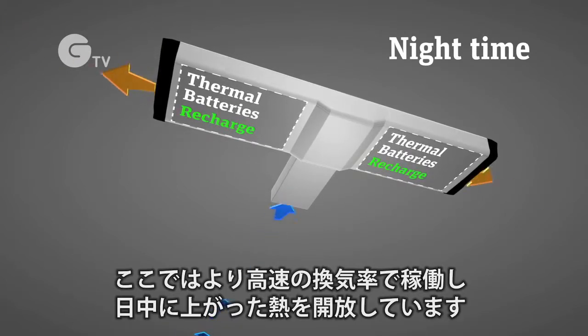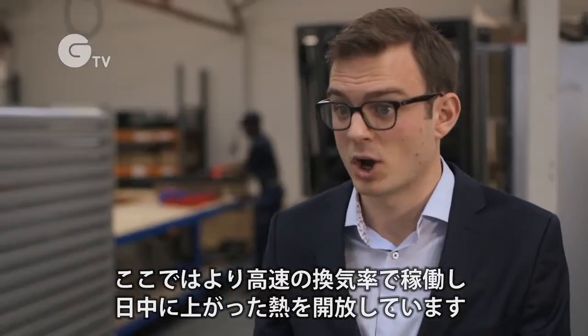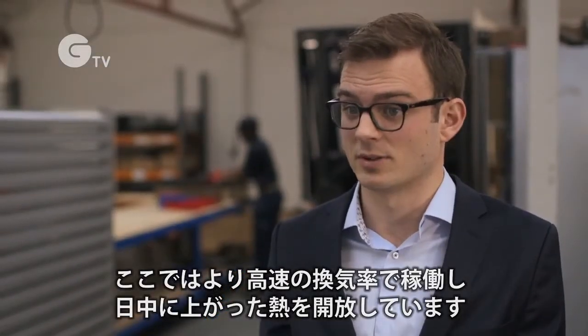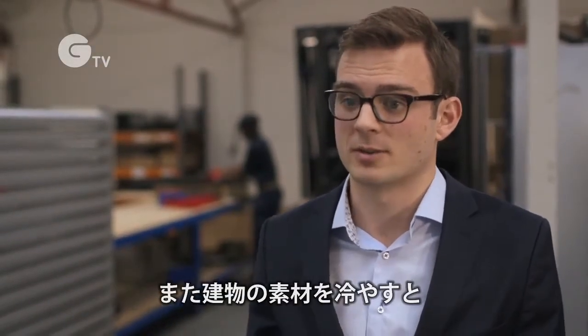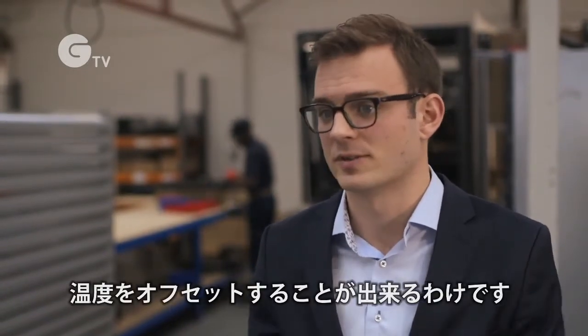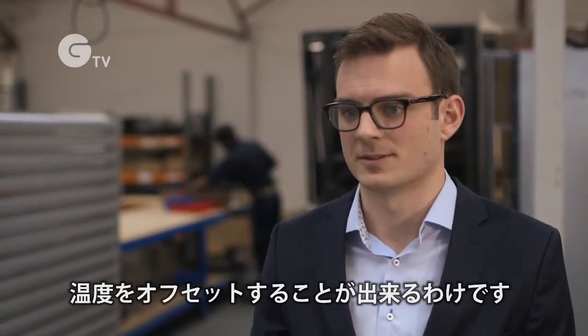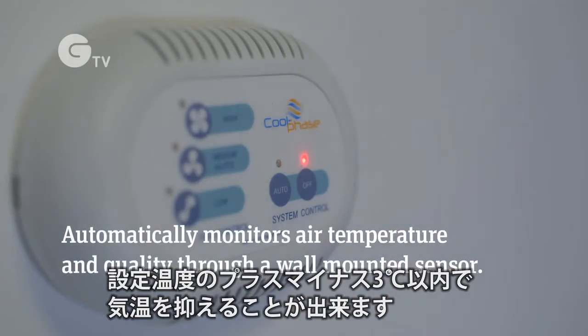So in this case, we're running on a higher ventilation rate, we're purging the building, releasing that heat that's built up during the day, but also cooling down the fabric of the building such that we can offset the temperatures the following day. We can typically condition a space to within plus or minus 3 degrees of the optimum comfort set point.